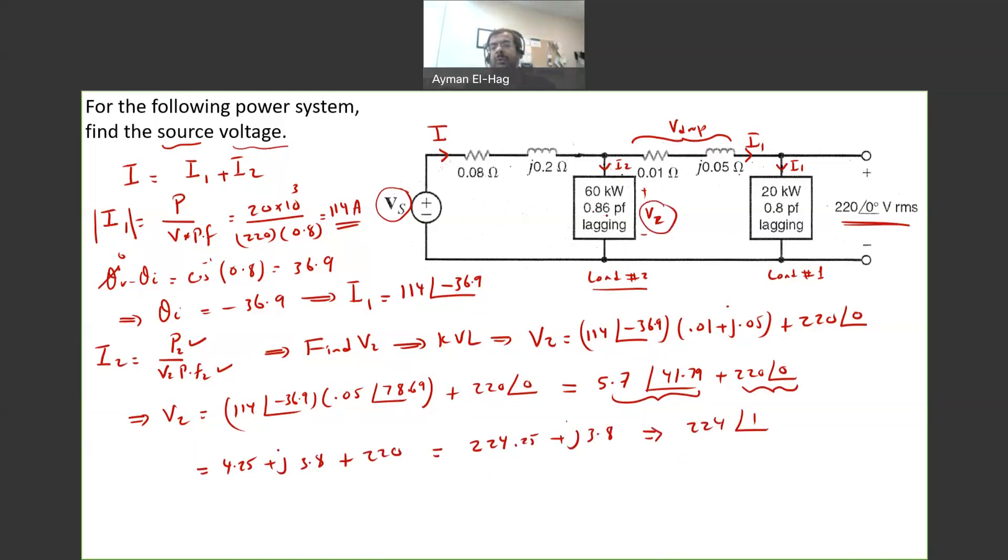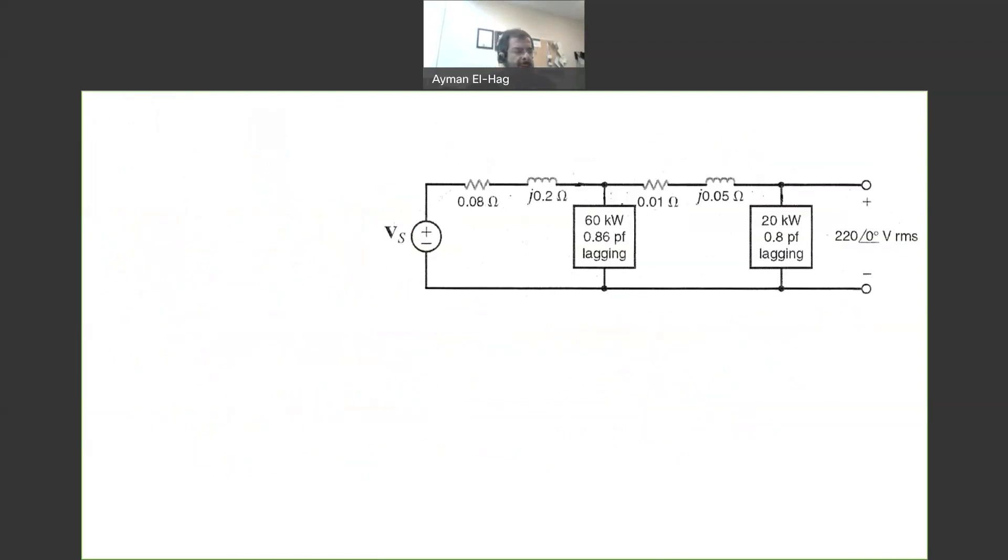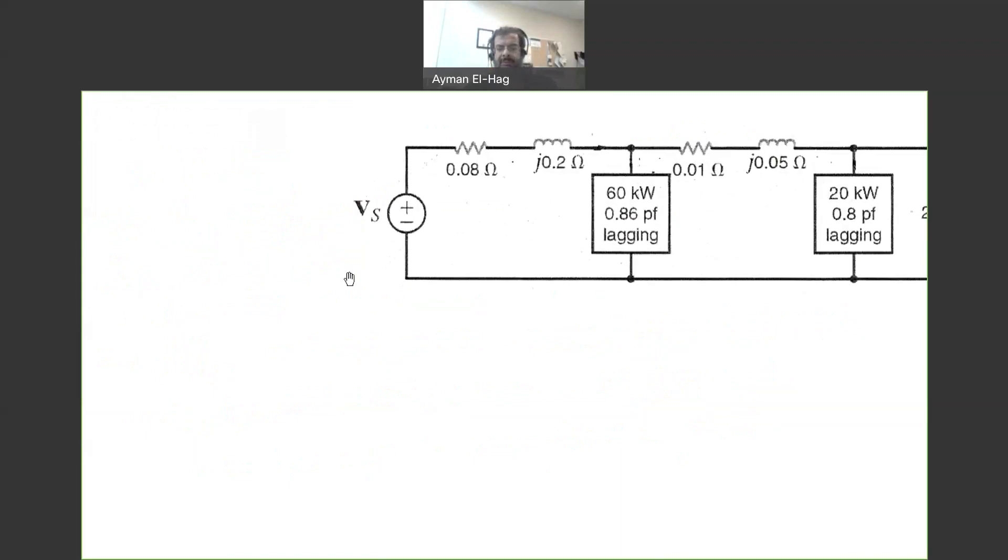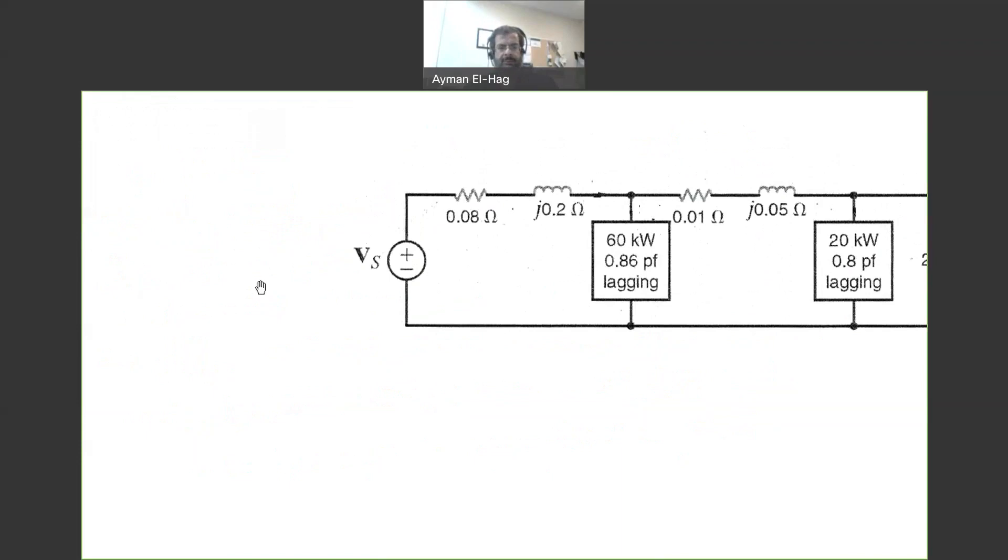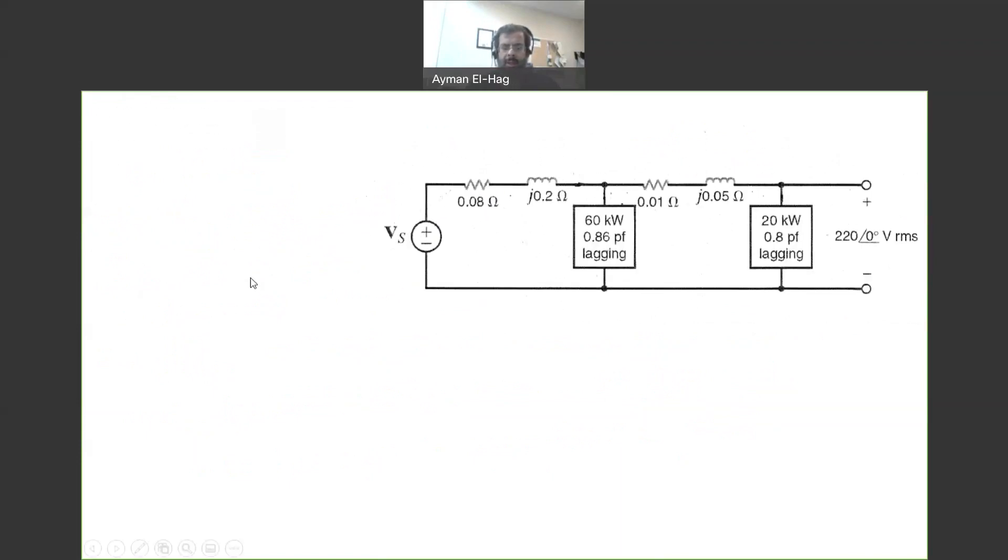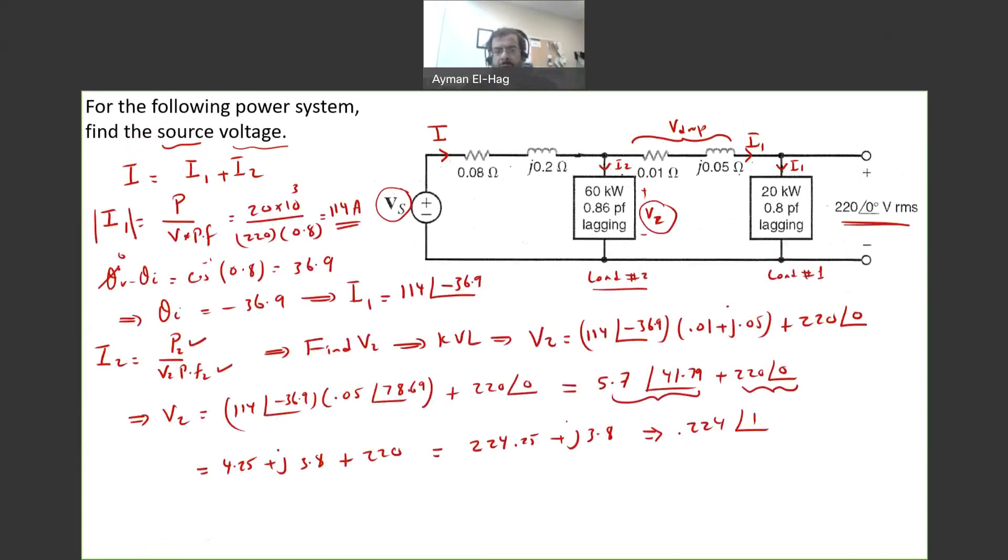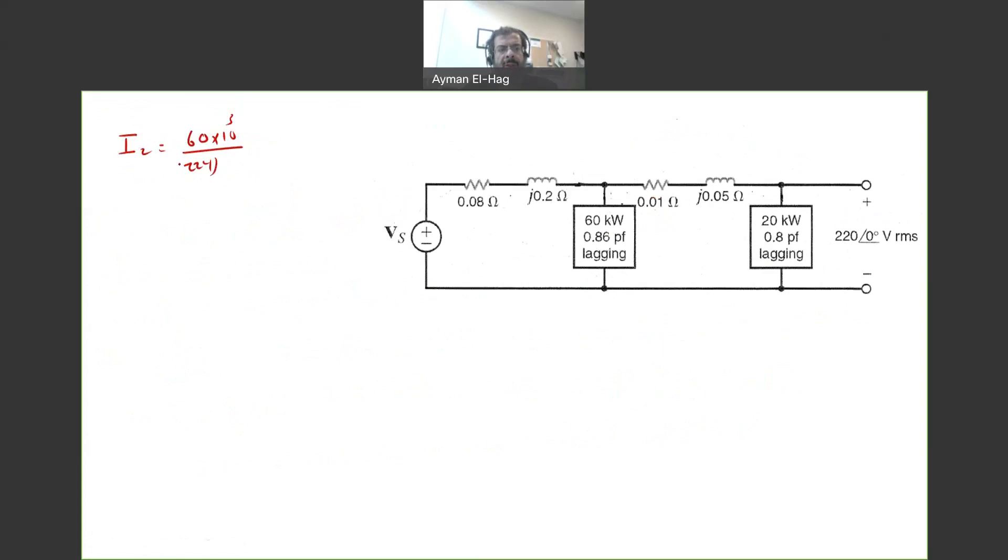Now I have V2. I can find I2. I want to find now my I2. My I2 is equal to the P2, which is the 60 times 10 to the power of 3, divided by the voltage, which is calculated here, which is 224, times the power factor, which is 0.86. And this is equal to 311.